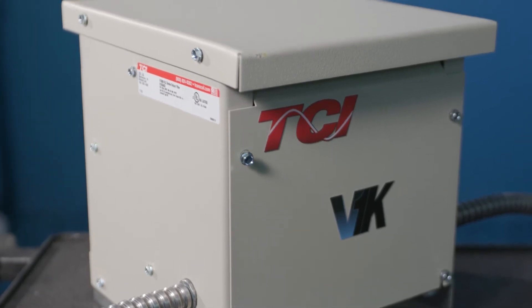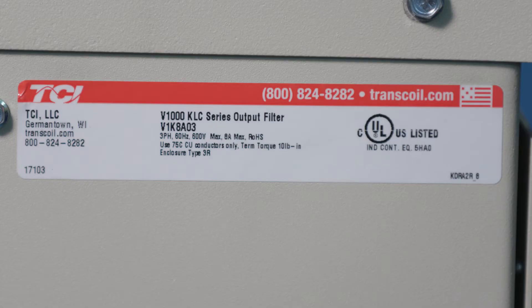For submersible water pumps, a dv/dt filter is generally recommended. Select your filter by matching the amperage and voltage of the system to that of the filter. Also, ensure the enclosure rating is suited for the application.